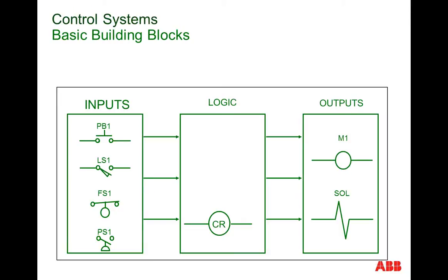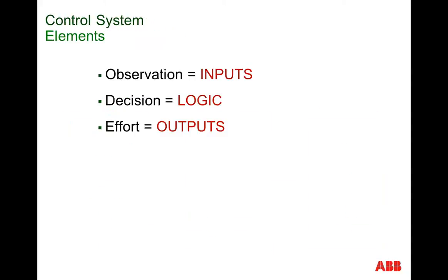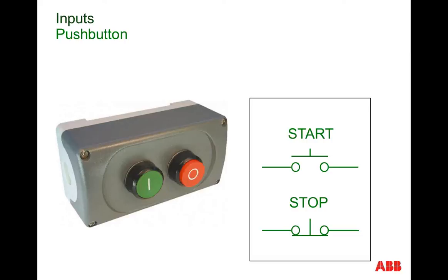Okay. Now let's take a look and see what a typical building block would be of control systems. First of all, we start with the basic building blocks of a typical control system: input, logic, and output. Inputs can be push buttons, limit switches, pressure switches. That's all shown with the symbols on the left. Outputs can be motor starters, solenoids or actuators, pilot lights, things like that. And the logic block typically consists of control relays and timers which establish the sequence of action through which the use of basic logic is done. And then finally outputs, the actuators that are shown on the right. In this case, a motor starter or device starting an electric motor, or the symbol for a solenoid, which is an actuator. Let's bring back our basic definition of control and point out that inputs provide the observation of our systems, logic devices provide the decisions, and then the output devices provide the outputs to the system.